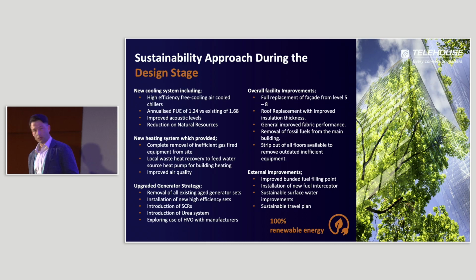General improved fabric performance—anywhere we go into, we're replacing walls with new walls, including white walls. Our data hall now has a box-in-box solution with outside cladding, an offset of about 300 millimeters, and new white walls installed, so heat gain into that area is minimal and gives us tighter control on that environment.